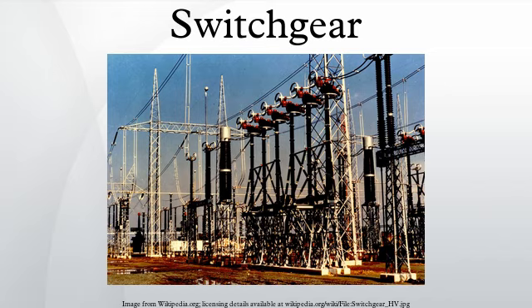Carbon dioxide breakers, which use carbon dioxide as the insulating and arc-extinguishing medium, work on the same principles as an SF6 breaker. By switching from SF6 to CO2, it is possible to reduce the CO2 emissions by 10 tons during the product life cycle.